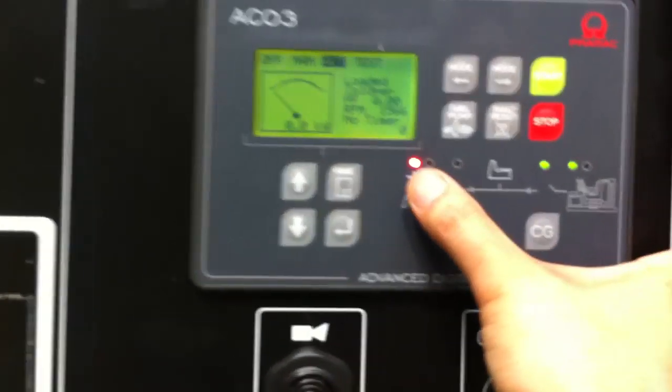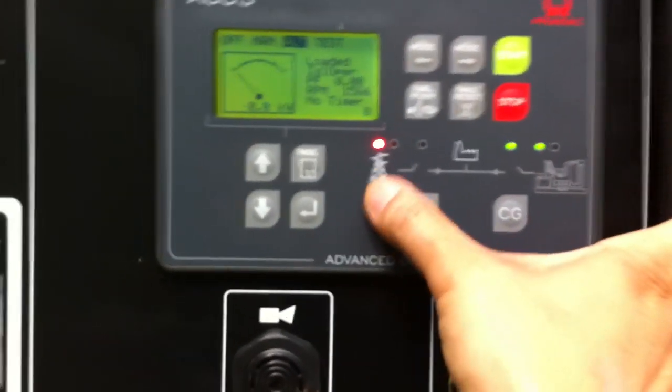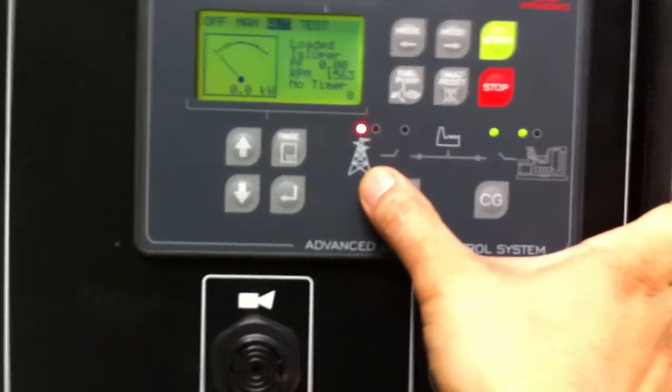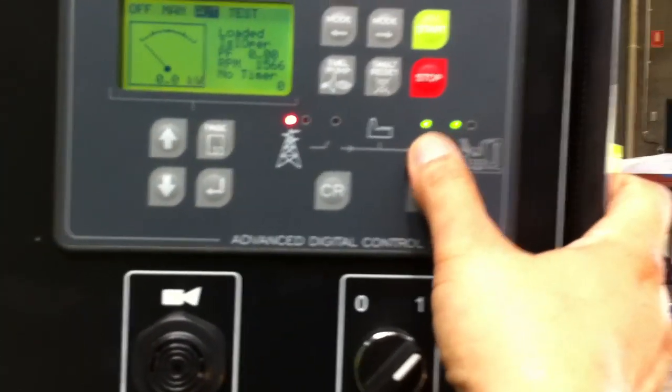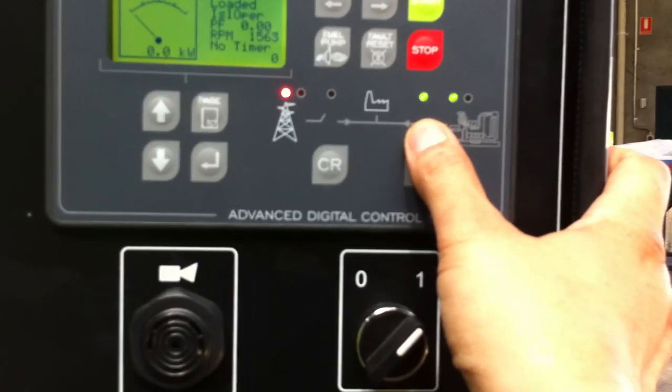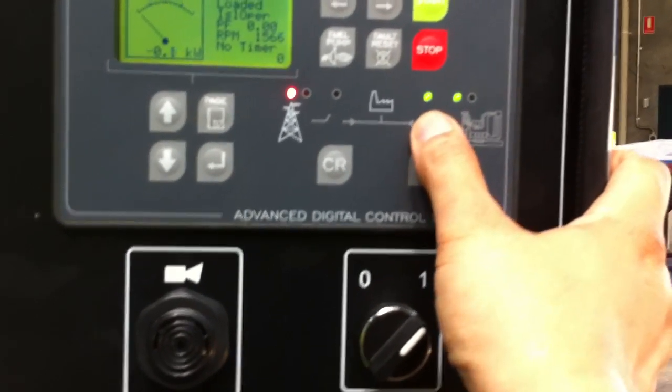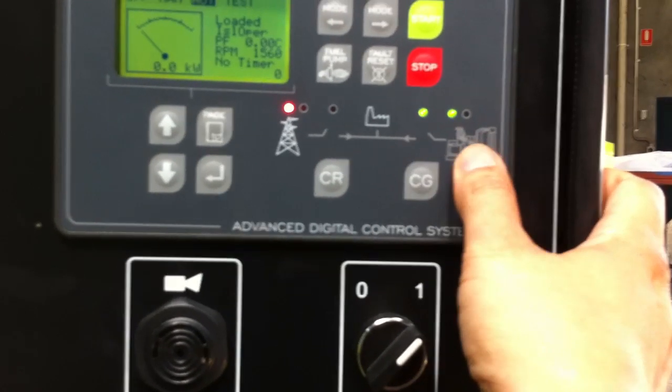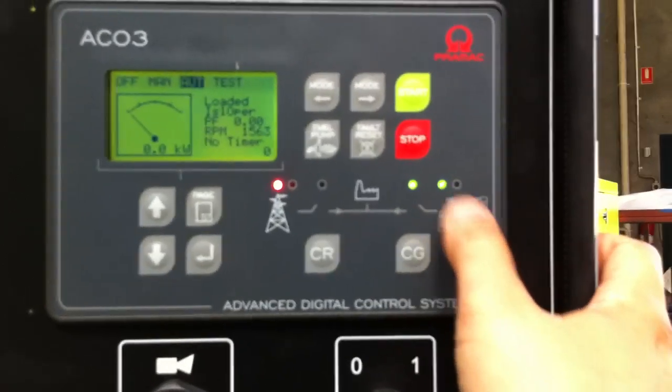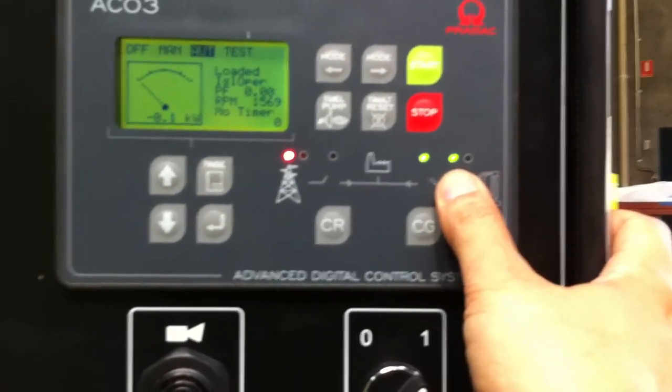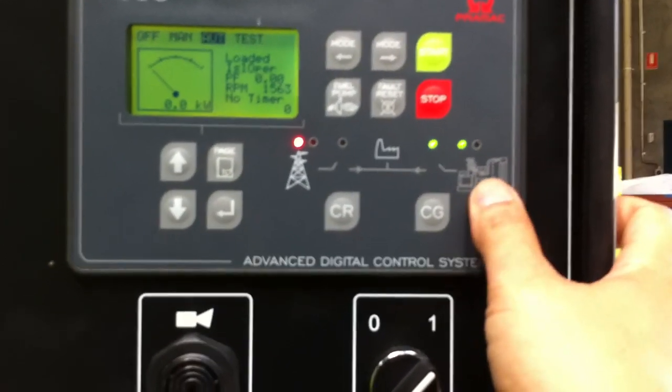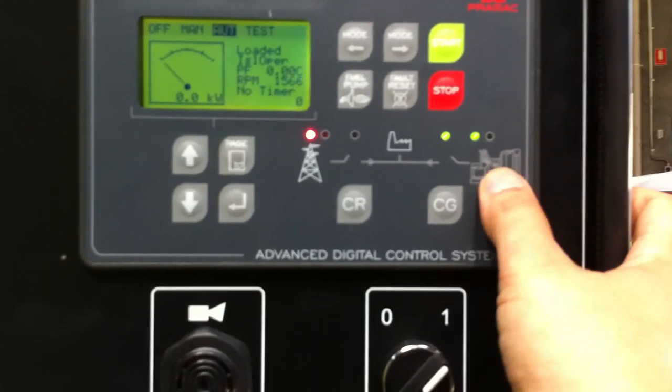You'll notice here that there's a red light for mains, so there's no mains power. Green light here for the ATS panel being supplied power from the generator side of the switch. And the generator is green, which means that it's supplying power from the alternator.